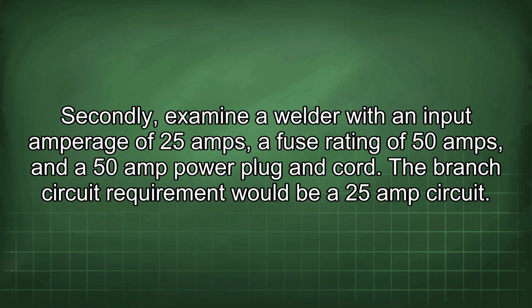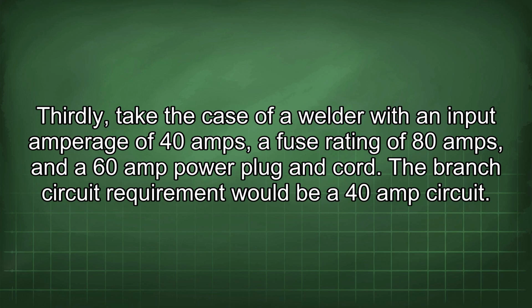Secondly, examine a welder with an input amperage of 25 amps, a fuse rating of 50 amps, and a 50 amp power plug and cord. The branch circuit requirement would be a 25 amp circuit. Thirdly, take the case of a welder with an input amperage of 40 amps, a fuse rating of 80 amps, and a 60 amp power plug and cord. The branch circuit requirement would be a 40 amp circuit.